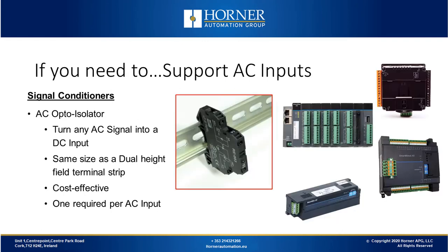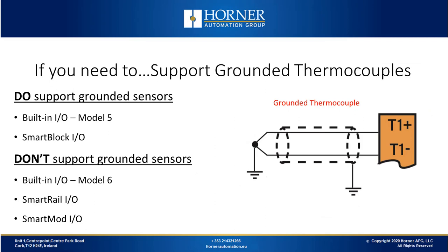If you need to support AC inputs, we have a Signal Conditioner, which is an opto-isolator that is AC on the input side and DC on the output side. It can turn any AC signal into a DC input and is very cost-effective — only one is required per AC input. For grounded thermocouples, the products that support grounded sensors include the built-in IO Model 5, which supports up to two channels of thermocouple on any XL product and they can be grounded or ungrounded. SmartBlock offers grounded thermocouple support as well, with 8-channel or 4-channel options. Products which don't support grounded thermocouples but do support ungrounded thermocouples include the built-in IO Model 6, the SmartRail IO thermocouple module, and the SmartMod IO thermocouple module.